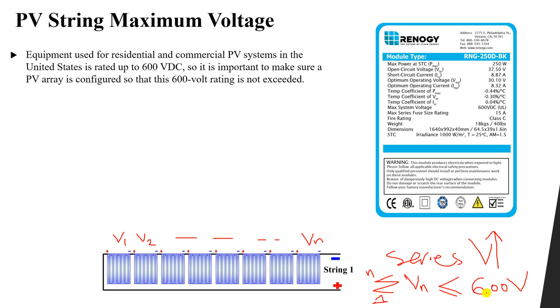In the United States, for residential and commercial PV systems, the maximum system voltage is rated up to 600V. It is important to make sure that a PV array is configured so that this 600V rating is not exceeded, according to the manufacturer or the module specifications.